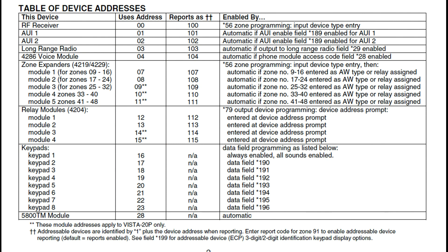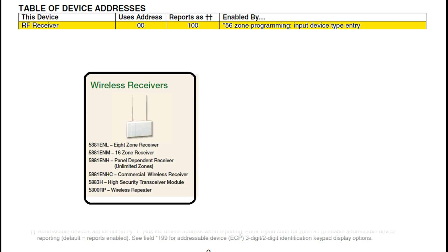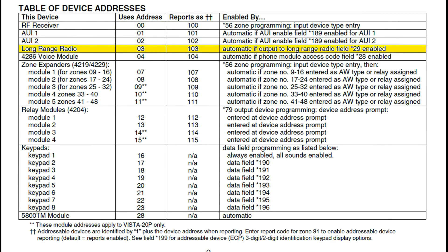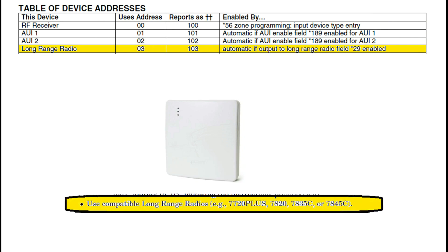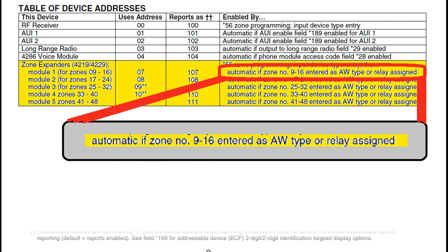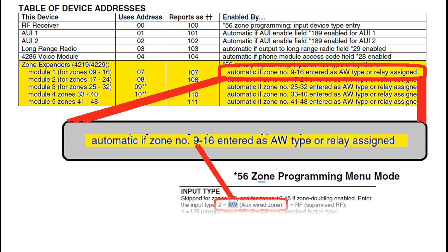Let's take a look at some of the other devices that require addresses. Address 0 is reserved for RF devices — RF stands for Radio Frequency. This will be your wireless receivers, as well as keypads that have wireless receivers built into them. Address 3 is Long Range Radio — these are devices that use a radio instead of a landline or phone line to communicate with your service provider. Address 4 is for the voice module. Addresses 7 through 11 are for zone expanders. The enabled-by note for address 7 states automatic if zone number 9 through 16 is entered as AW type, or the relay is assigned. Zones 9 through 16 are the zones that will be used on your first expander module. While setting up the module, you enter star 56 to program the zone. In the Input Type field, select 2, which will give you AW or AUX wired zone.